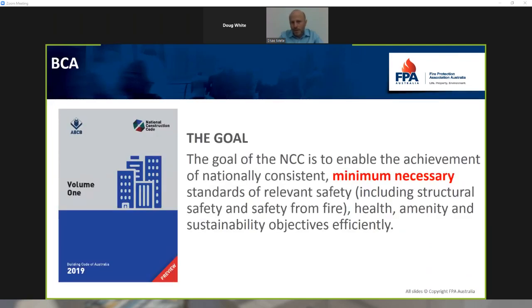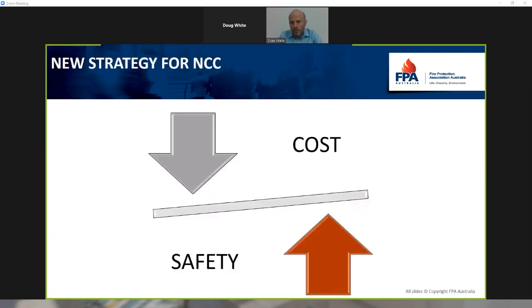The other one is the BCA. So there is this shift now towards the minimum necessary aspect of the BCA, where the Australian Building Codes Board is saying that, yep, we've got to build these systems to this minimum level. And if you want to go beyond that, you're welcome to do that, but you have to meet this minimum level. So it's not about building the gold-plated sprinkler system for all occupancies. It's got to be fit for purpose. So obviously that's about cost, and this is something that a lot of people in our industry always think is a secondary issue, and I guess it is the secondary issue, but it's a close second, right behind number one, because ultimately, if you don't make these systems cost effective, you will not get change in the industry, which we've come to know now thoroughly.